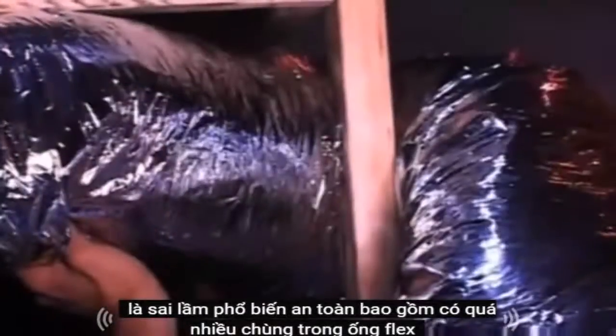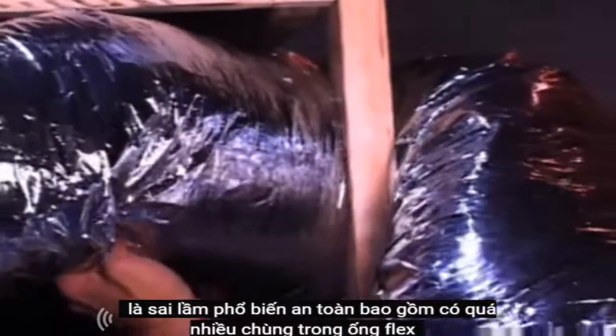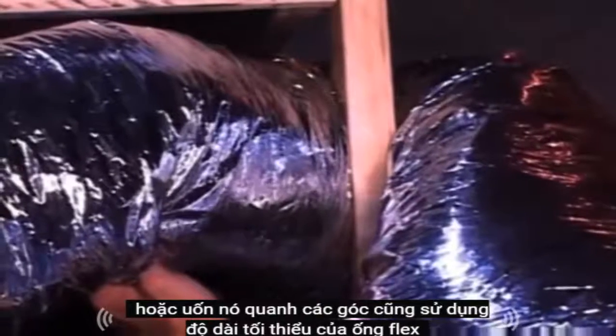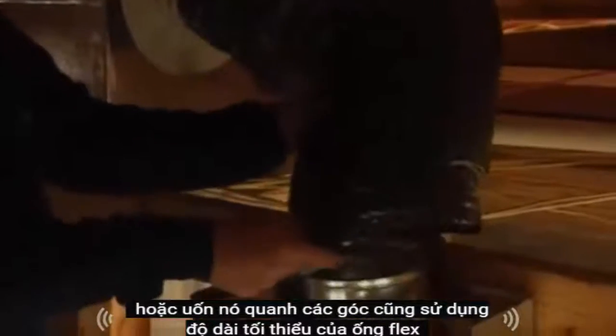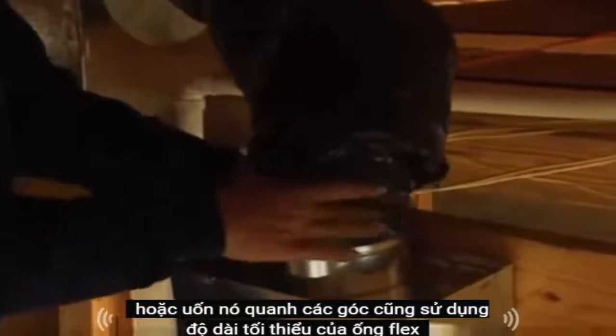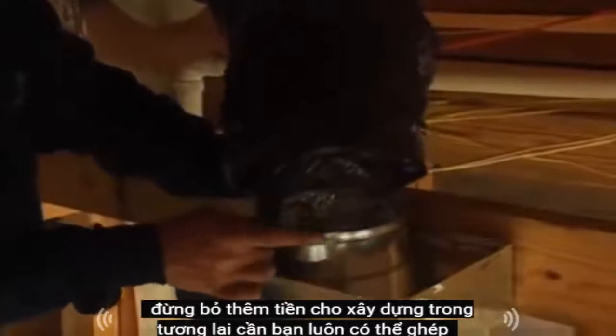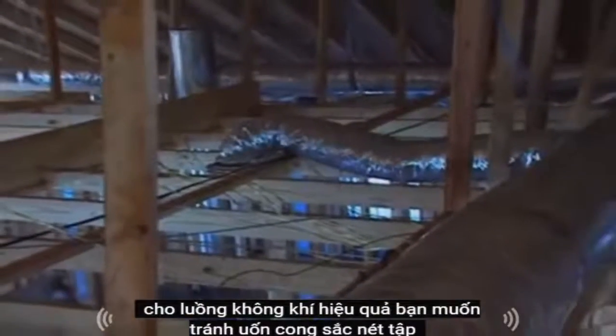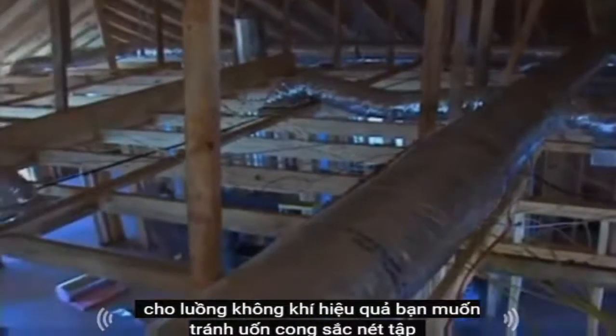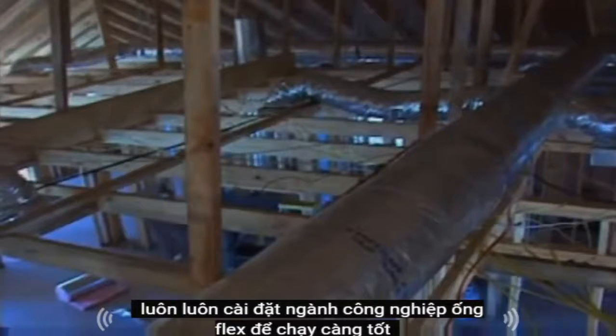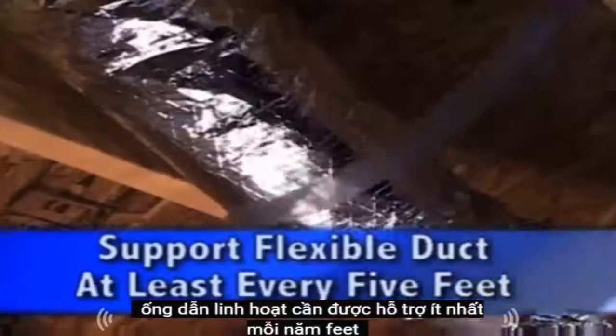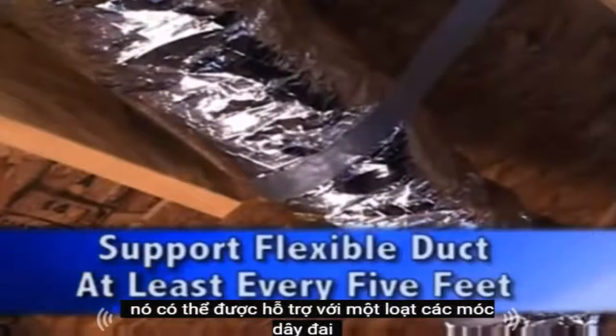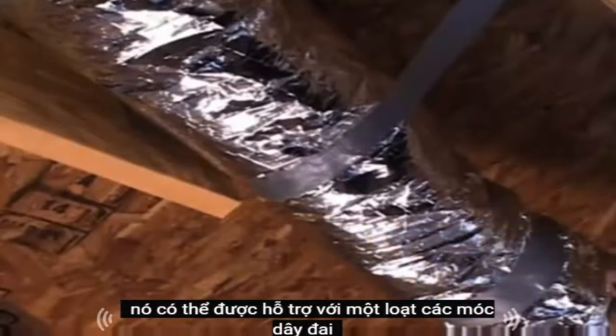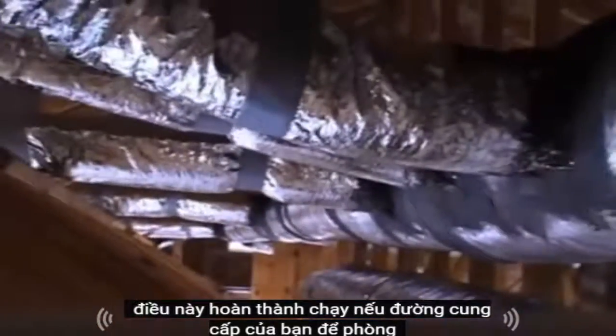Common mistakes include having too much slack in the flex duct or bending it around corners. Also, use the minimum length of flex duct. Don't leave extra for future construction needs. You can always splice it in. For efficient airflow, you want to avoid sharp bends and turns. Always install flex duct in as straight a run as possible. Flexible duct should be supported at least every 5 feet. It can be supported with a variety of hanger straps. This completes the run of your supply line to the room.